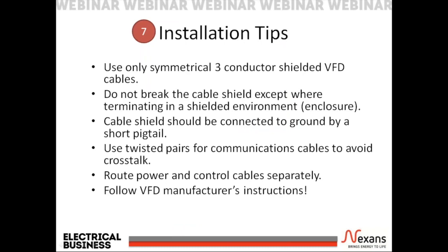There are a few key items to remember when it comes to VFD cable installation. Use only symmetrical, three-conductor shielded VFD cables. Do not break the cable shield, except where terminating in a shielded environment, inside the metallic equipment enclosure, for example. The cable shield should be connected to ground by way of a short pigtail at both ends of the VFD cable. Remember, this is the return path for the high frequency currents. Use twisted pairs for communication cables to avoid crosstalk.